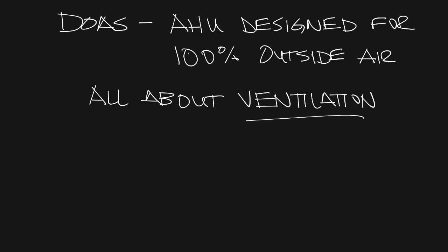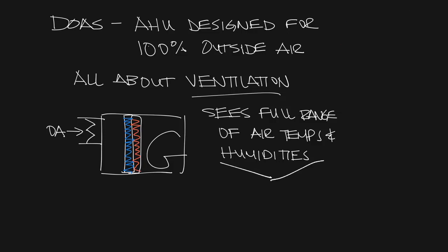Rather than bringing in a fraction of its supply air from outdoor air through the economizer, the DOAS has a large outdoor air intake that is designed to provide all the necessary filtering, dehumidification, heating, and cooling necessary to use outdoor air.